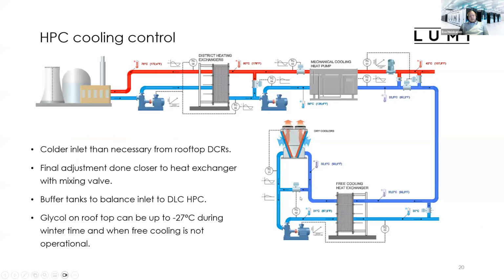Key point of operating this free cooling unit here is to having this antifreeze mixing valve, which is close to the heat exchanger, so it can make much faster adjustments closer to the heat exchanger than in the rooftop. So especially in the winter time, we are able to have a pretty cold liquid from the rooftop to this mixing valve. So we are mixing the outlet from the heat exchanger, the inlet from the DCRs to maintain the 31 degree Celsius on the inlet side of the heat exchanger to keep the stable 32 degree outlet on the primary cooling loop.